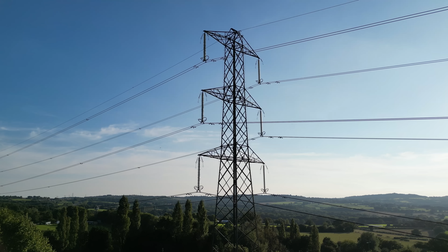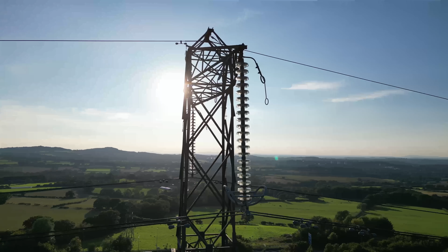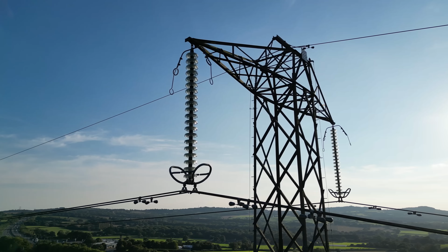These lines originally ran at 275 kilovolts, but many were later upgraded to 400 kilovolts, or about 1,000 times domestic voltage. Because of the higher voltages, the insulator strings are longer, with more discs. They also have twin conductor cables for more current capacity. According to my best information, at 400 kV these can handle up to about 1500 megawatts per circuit of 3 conductors.